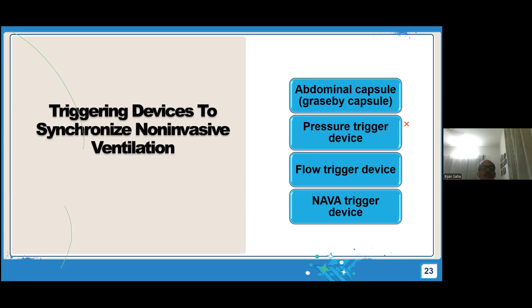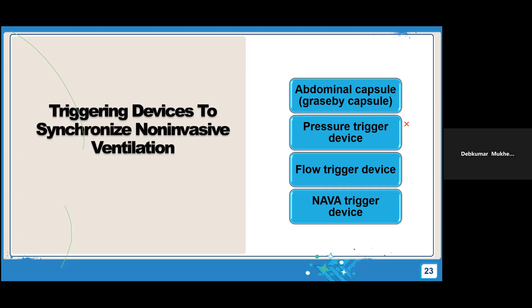I think you are correct that if you use a flow sensor, the work of breathing will be less. But there are some inherent problems of flow sensors in the case of non-invasive positive pressure ventilation. So we'll discuss. The triggering devices used to synchronize non-invasive positive pressure ventilation are the abdominal capsule or Graseby capsule, the pressure trigger device, the flow trigger device, and the NAVA device. Next slide, please.